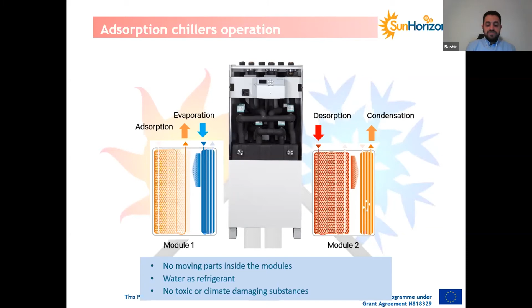adsorption system consists, other than the chiller, of three water circuits. The first one is the drive circuit, the heat, which is in the form of hot water at a temperature from 60 or even lower up to 95 degrees. In Sun Horizon, we are using solar heat, but we can also use any other type of waste heat.